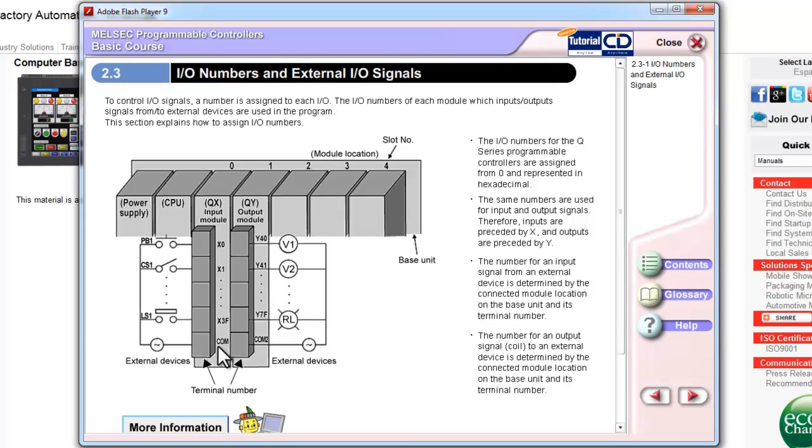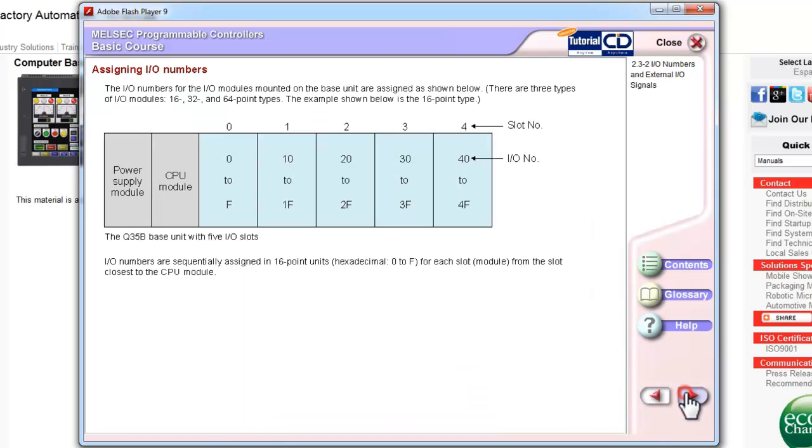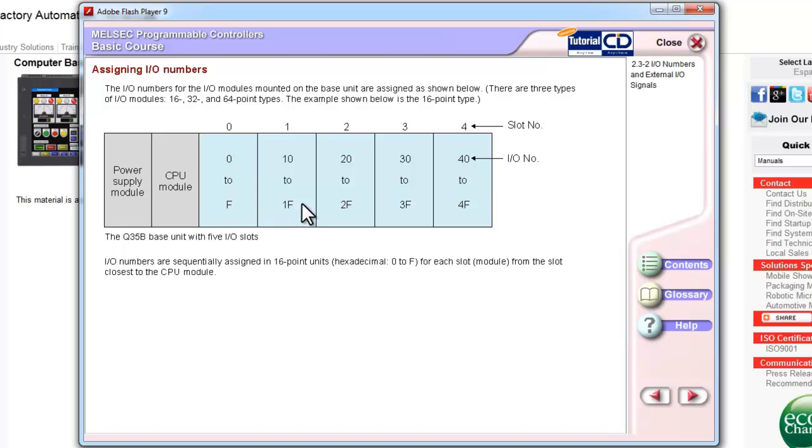For L Series and Q Series, everything is organized in hexadecimal format. So, for example, if I go to the next page here, you can see with 16 point IO modules, I would have 0 through F in one slot. The next slot would occupy 1 0 to 1 F, and the next would occupy 2 0 to 2 F, etc.